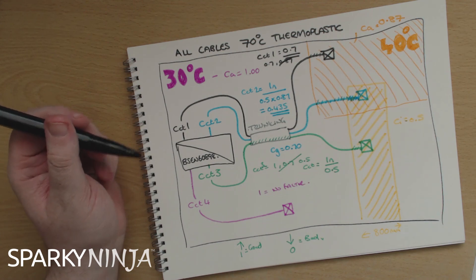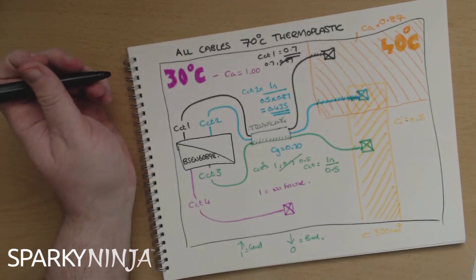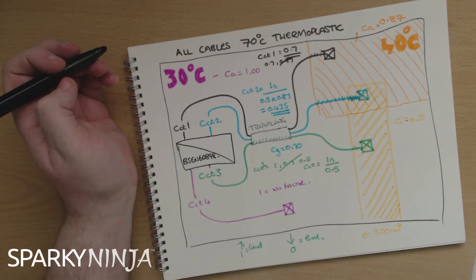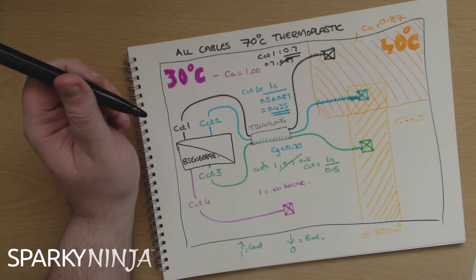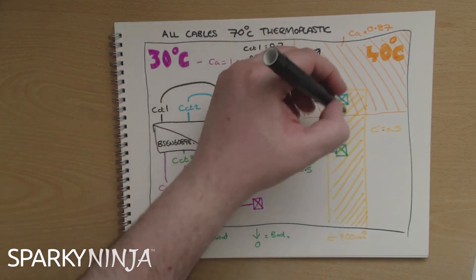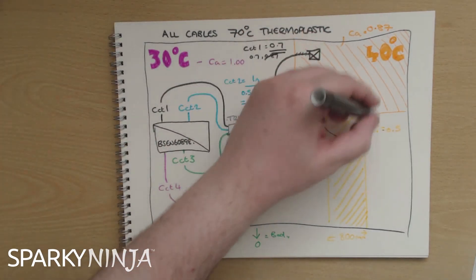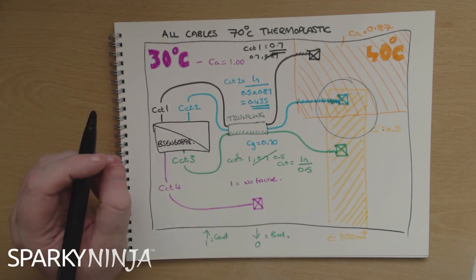Big changes from little different methods of installation. When using correction factors, identify them and only combine them if they coexist — if they happen at the same place at the same time. Otherwise you'll make the cable bigger for no reason.